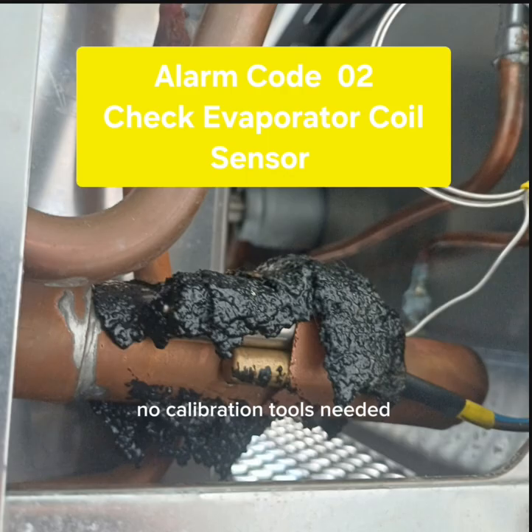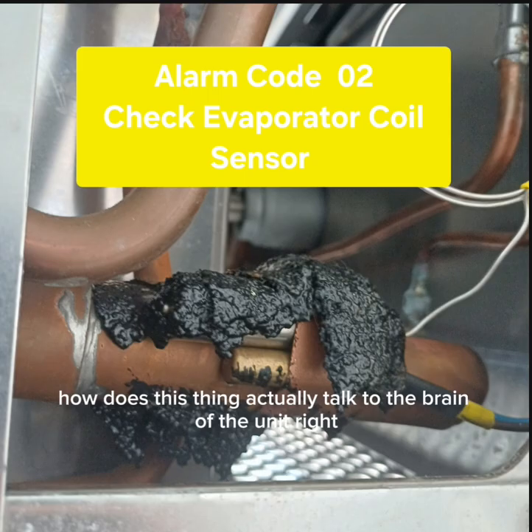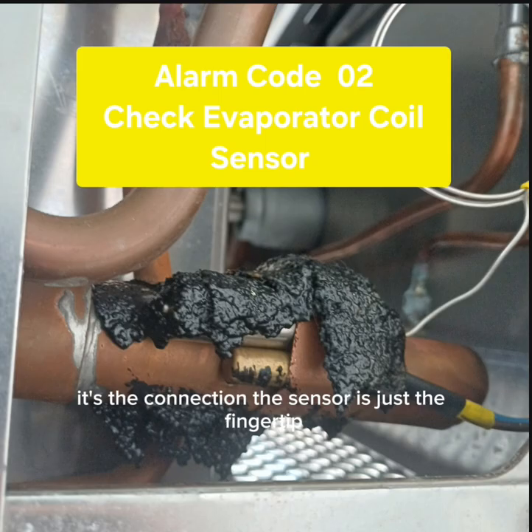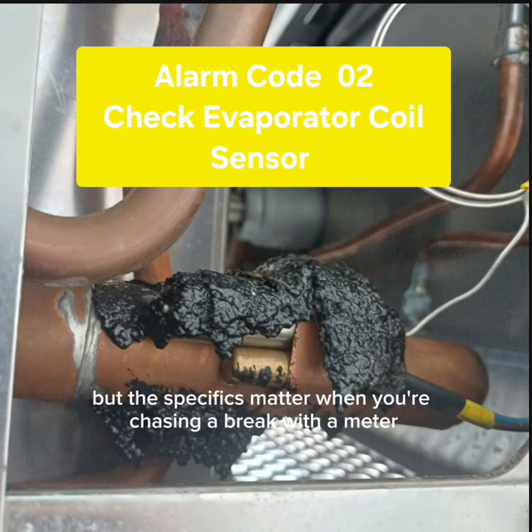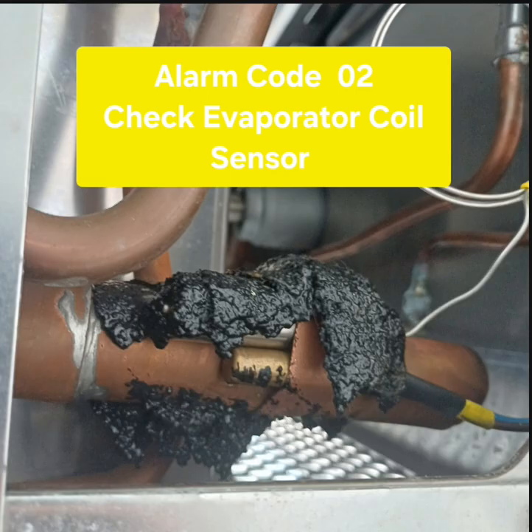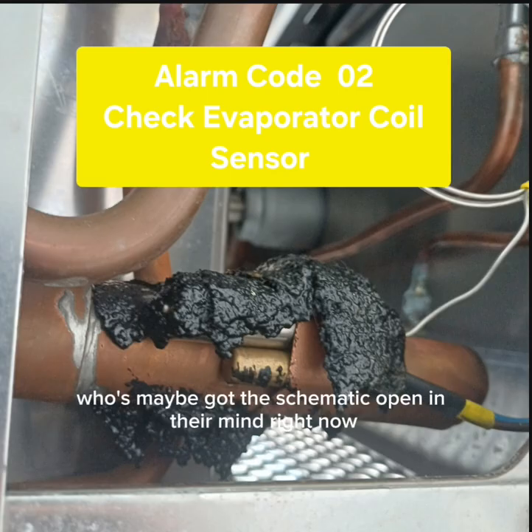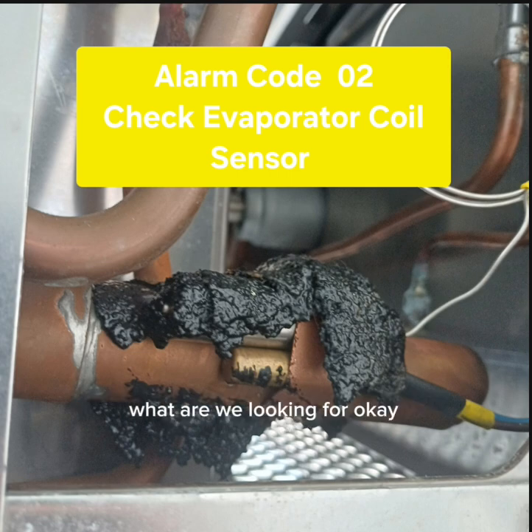No calibration tools needed. So we're at the evaporator coil. Let's talk about the nervous system. How does this thing actually talk to the brain of the unit? Right, because it's usually not the sensor itself that failed, it's the connection. The sensor is just the fingertip, the wiring is the nerve. It's a simple 2-wire circuit, but the specifics matter when you're chasing a break with a meter. So let's map it out. For the listener who's maybe got the schematic open in their mind right now, what are we looking for?